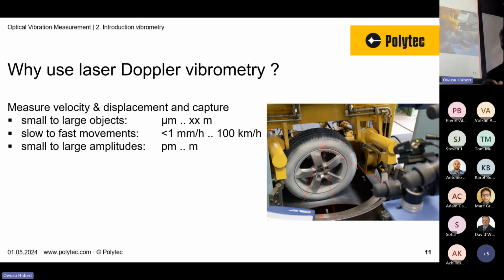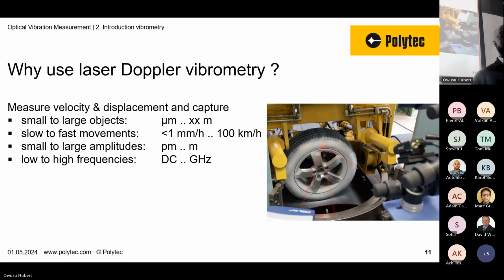It has a deep capability to reach the amplitude you require, as well as slow to high frequency. One thing about our instrument is it goes up to DC, meaning zero, so we can measure from 0 Hertz upwards. There's no limitation when you want to capture something in the lower frequencies, which is sometimes really challenging for traditional conventional instrumentation out there.